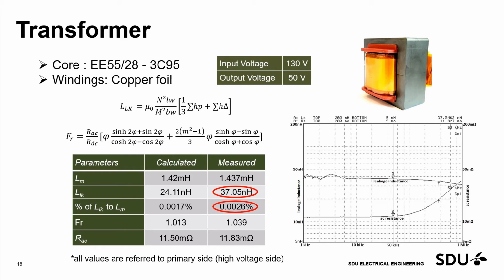It's about 37 nanohenry for the leakage inductance, which is extremely small for this type of transformer. Since we don't want that leakage inductance anyway, it's better not to have it, but it's almost impossible to eliminate completely. As a transformer designer, you know up to 1% leakage inductance is accepted, but here it's only 0.0026. You can get this calculation before building the transformer by using these equations.